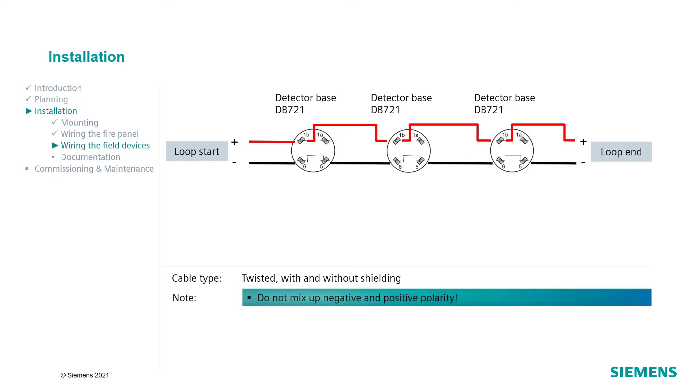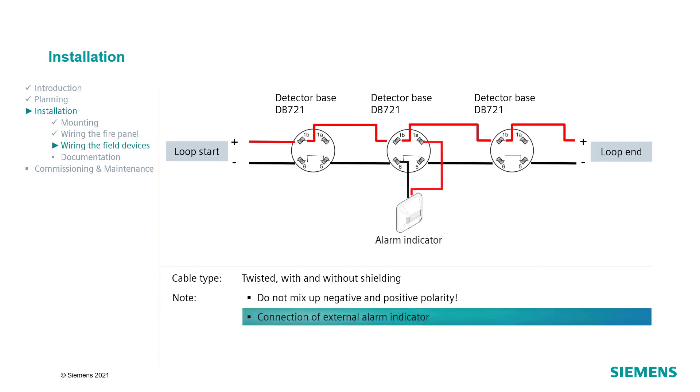First, wire the detector bases. Connect the negative and positive poles to the corresponding terminals in the detector base as shown in this graphic. The external alarm indicator can be connected to the terminals 1A and 6 and it can be configured how the indicator is activated, either alongside the detector's internal alarm indicator, using a zone alarm or using an independent control.